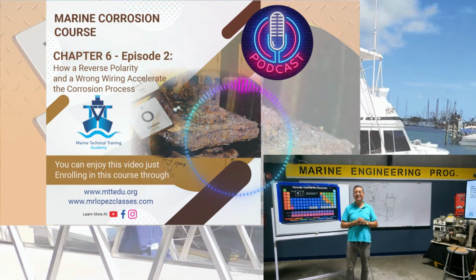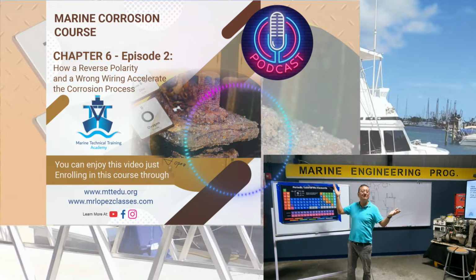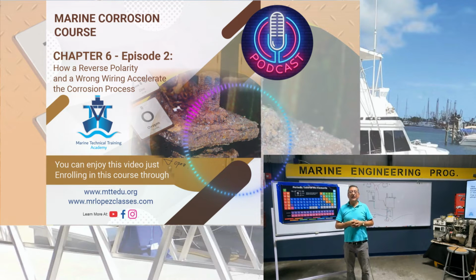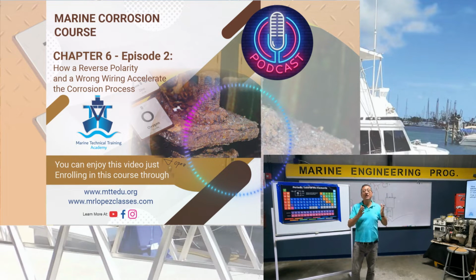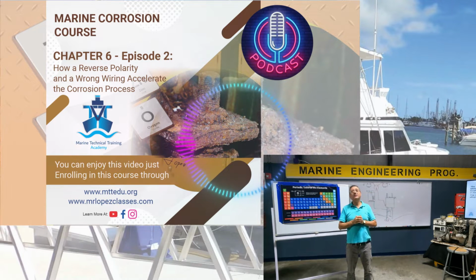Remember that the galvanic isolator inside the construction is diodes and capacitors. Remember that if you have diodes to block current, that current you block, as you remember in electronics, should be stored in a capacitor, and the capacitor drains through the bonding. For that reason, the case of the galvanic isolator should be connected to the bonding. Normally, with the bigger galvanic isolators, the case is metallic, and that case should be connected to the bonding also.